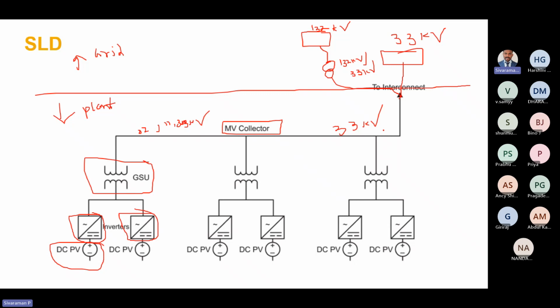Okay, so a large-scale ground-mounted solar PV system, more than 50 or 60 megawatt, will mostly be connected to high voltage and extra high voltage. In those locations, we need a power transformer, this one. Where the installed capacity is less than 50 megawatt and there is a medium voltage line up to 33 kV very nearby, in those locations a power transformer is not required. We can connect our power plant to the existing grid at that voltage level itself.